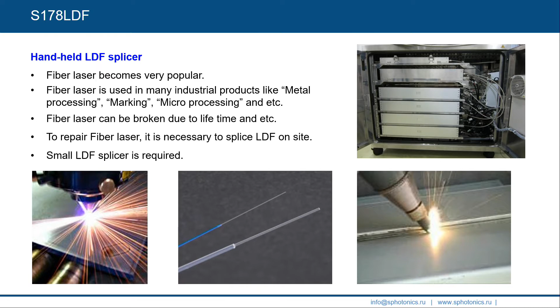So what is large diameter fiber? Large diameter fiber is used to transmit high power laser light in the field of medical devices and laser processing machines. The typical clad diameter of these fibers lies between 200 micrometers up to 1000 micrometers. You can actually meet some specialty fibers with even more than 2 millimeter diameter cladding. Recently the demand for large diameter fibers is increasing.